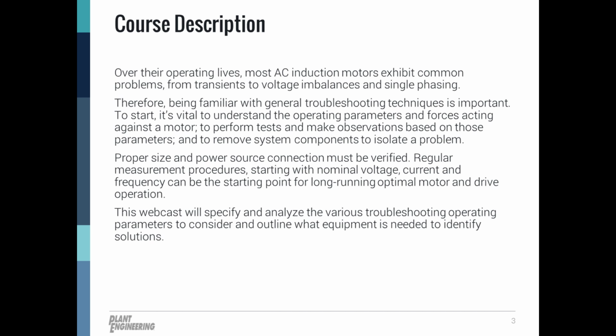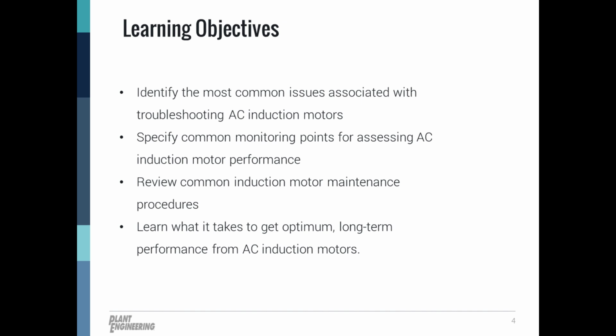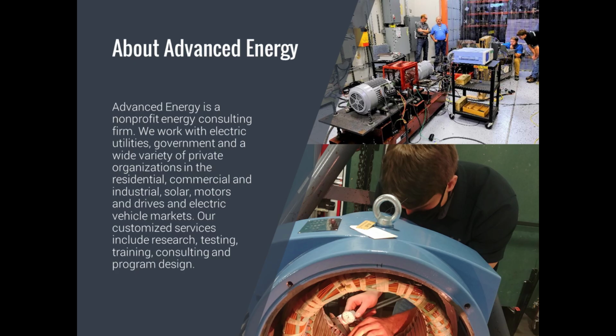Over their operating lives, most AC induction motors exhibit common problems, from transients to voltage imbalances and single phasing. Therefore, being familiar with general troubleshooting techniques is important. To start, it's vital to understand the operating parameters and forces acting against a motor, to perform tests and make observations based on those parameters, and to remove system components to isolate a problem.